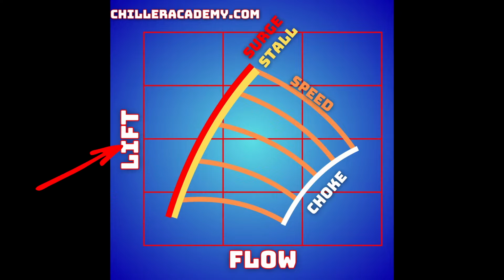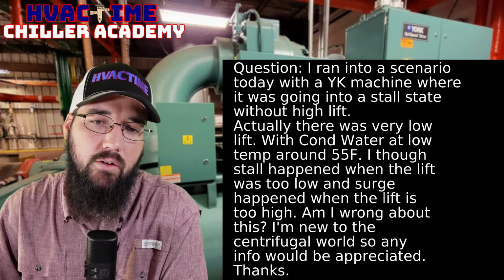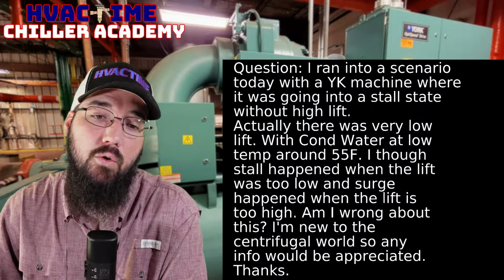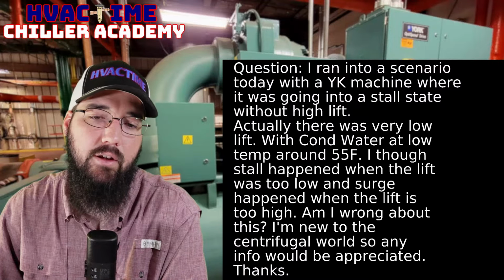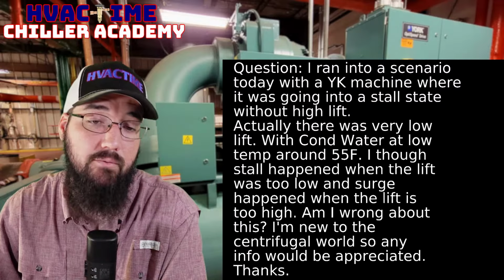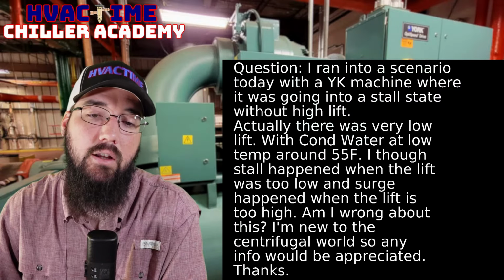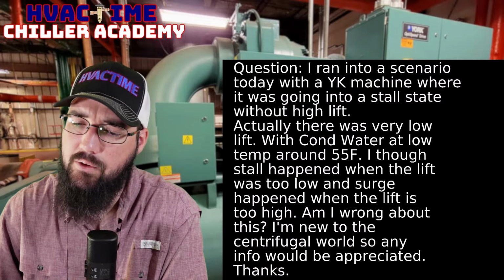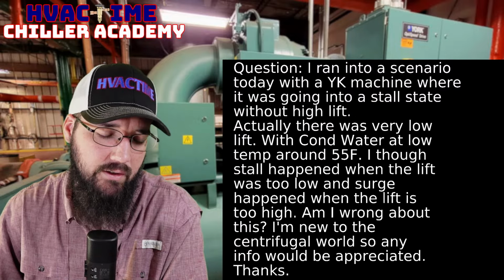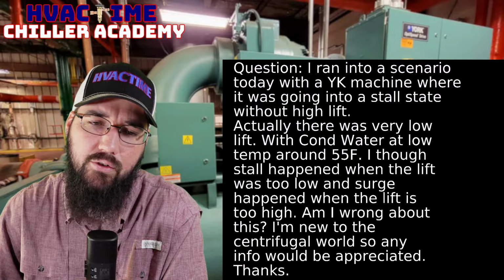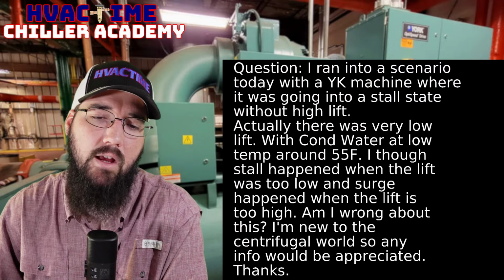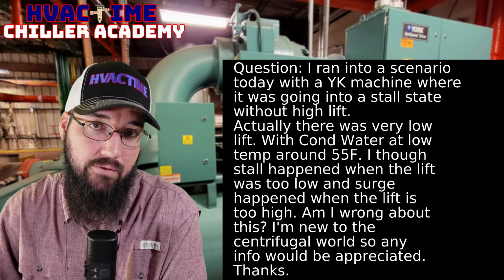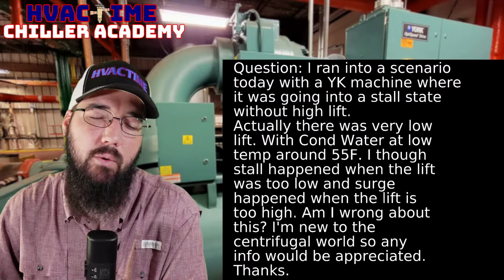Now, if you look, we have lift, we have flow. Okay. Depending on your condition, coming back to the question, we're pointing out that we have a low lift condition. We know we have low lift because we have really cold condenser water coming in, which a YK can do down to, I know, 60. I don't think a YK could do 55. I would have to verify that. I know that there are a lot of machines that can do 55. I don't remember if a YK can.